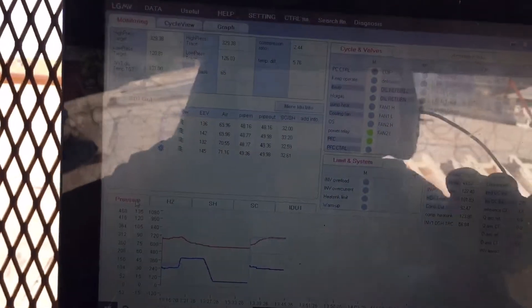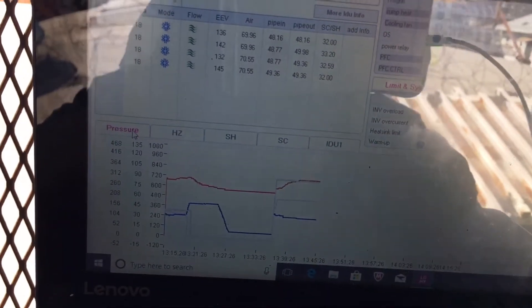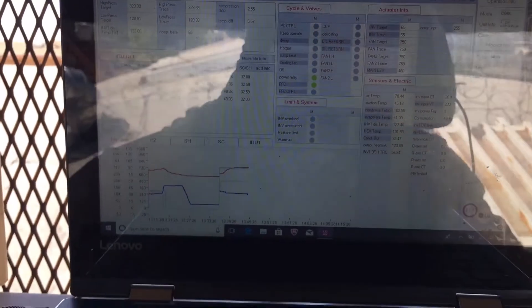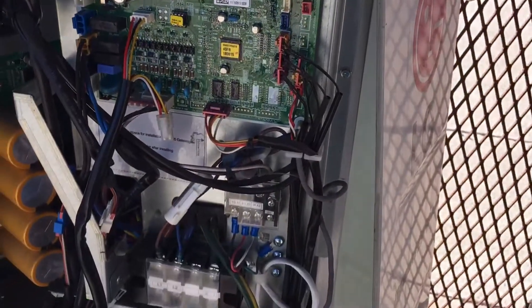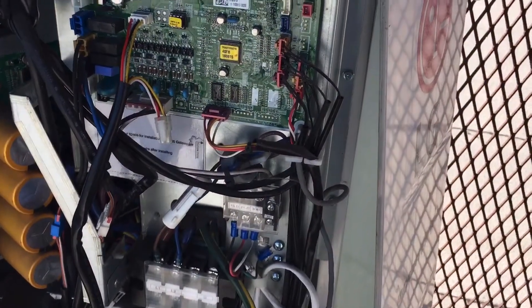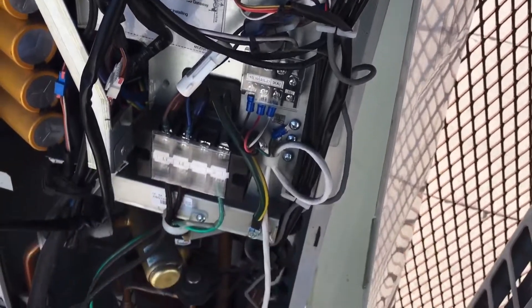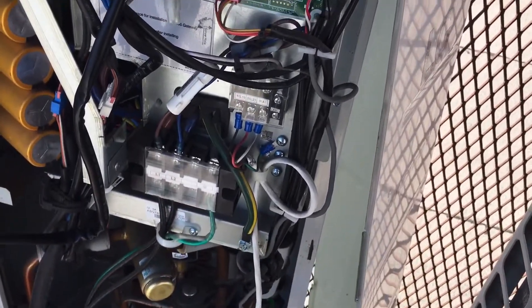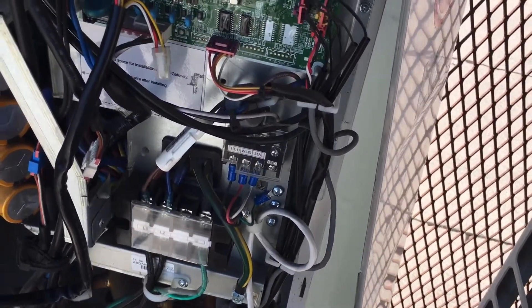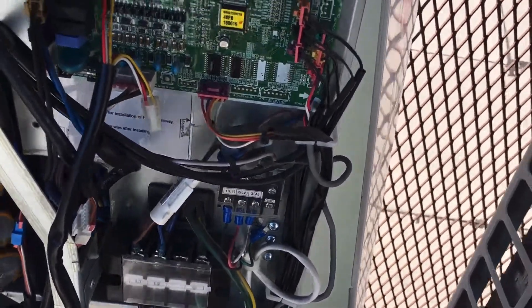You do not need your gauges because everything is handled right here. For the guys who say 'I'm going to try to use subcooling or superheat on one of these things,' don't even attempt it dude. It's just a lost cause because the factories have placed their temperature sensors in the areas they want them, where they know they should be taking the superheat and subcool.